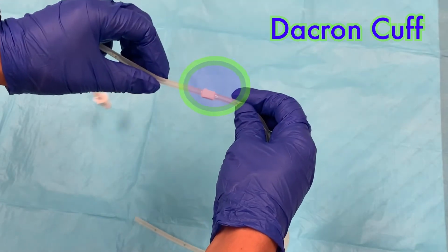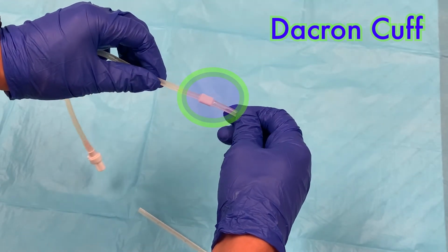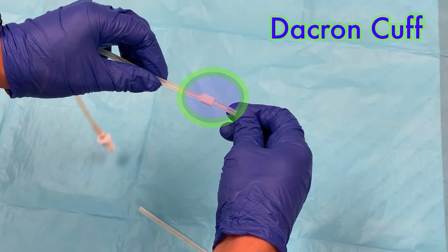In the middle of the catheter is the dacron cuff. This is a small cuff of material that serves first to help anchor the catheter in place in the patient, and also can be used as a warning sign that the catheter has been displaced. The dacron cuff should be located beneath the patient's skin and should not be seen. If it is visible, the catheter has been pulled out, and placement should be confirmed before moving forward with drainage.